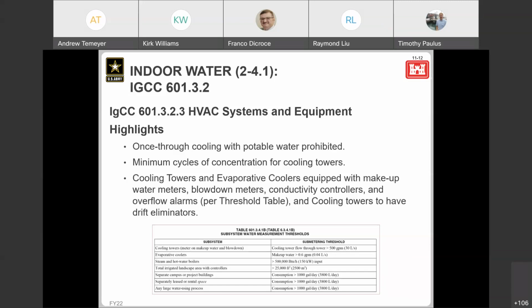And then the last one is cooling towers and evaporative coolers, equipping them with makeup water meters, blowdown meters, conductivity controllers, overflow alarms, and cooling towers have drift eliminators. So these are some real world things. This would be checking to make sure that your design includes all these things.